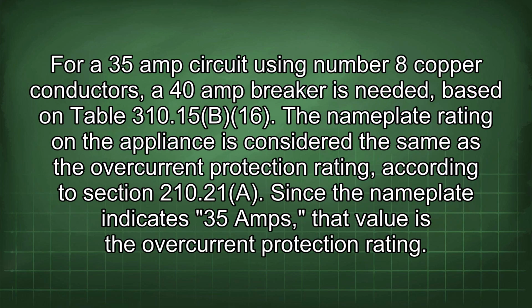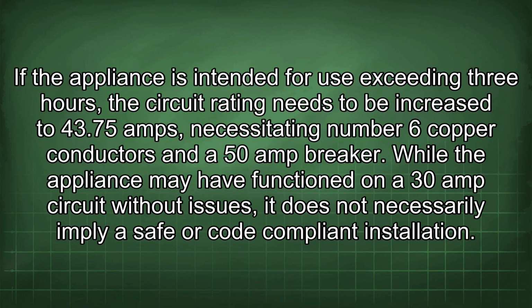For a 35 amp circuit using number 8 copper conductors, a 40 amp breaker is needed, based on table 310.15(B)(16). The nameplate rating on the appliance is considered the same as the overcurrent protection rating according to section 210.21(A). Since the nameplate indicates 35 amps, that value is the overcurrent protection rating. If the appliance is intended for use exceeding 3 hours, the circuit rating needs to be increased to 43.75 amps, necessitating number 6 copper conductors and a 50 amp breaker.